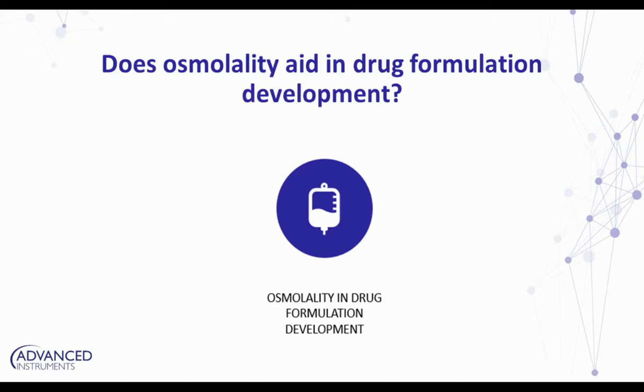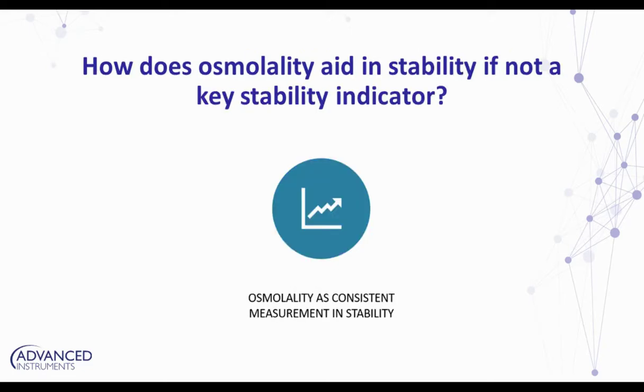Last but certainly not least, let's talk about the area of stability. Tara, could you talk about the consistency of an osmolality measurement and how it pertains to this really critical area of testing? It really is one of the things you can rely on with the osmolality measurement — there's not a lot of room for analyst error. So if we get a measurement that's out of spec or out of tolerance, it's pretty likely to be a rational result. I can instantly think of two examples where osmolality measurement helped us during an investigation into out-of-tolerance values during a stability study.